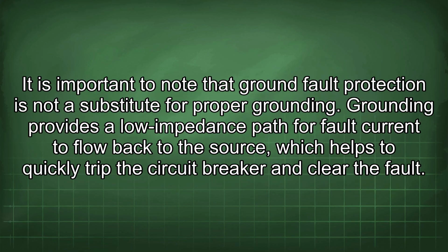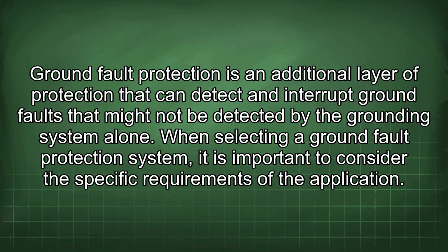It is important to note that ground fault protection is not a substitute for proper grounding. Grounding provides a low impedance path for fault current to flow back to the source, which helps to quickly trip the circuit breaker and clear the fault. Ground fault protection is an additional layer of protection that can detect and interrupt ground faults that might not be detected by the grounding system alone.